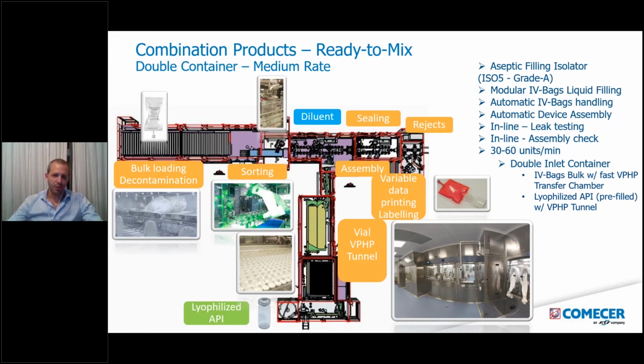So the challenge of this line, of course, was to handle two different types of package with two different types of automatic decontamination system. On the bag side, we were able to use already designed modules with a decontamination chamber and an automatic sorting system that singularizes bags before the filling of the liquid part.